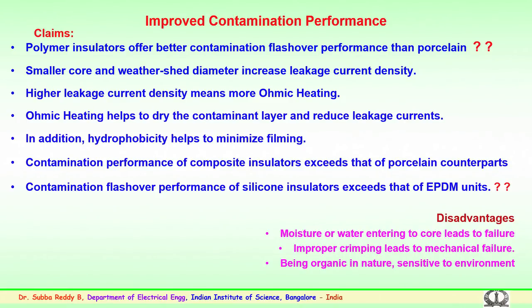This ohmic heating helps to dry the contaminated layer and reduce the leakage currents. The reason is, once the polluted layer formed on the insulator surface becomes wet, conduction happens, the surface becomes conductive and the leakage current flows. Because of the heating, with lesser surface area compared to the ceramic, the heating here is more. This helps to dry the contaminated surface. Further, once the surface dries, the dry band, or the formation of the dry area, offers a very high resistance and further reduces the leakage current flow. This is one of the major advantages because of the hydrophobic nature, the water repelling property of the polymer insulator, compared to the earlier ceramic or porcelain insulators.